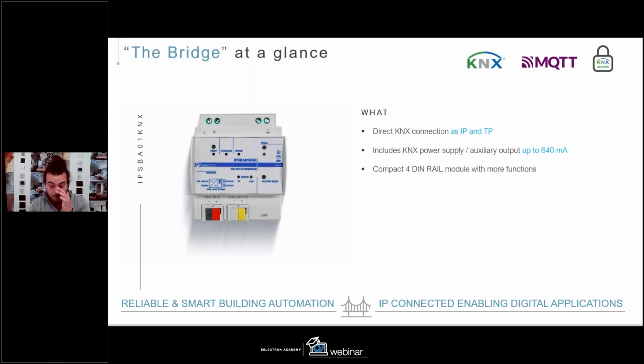Regarding this device, I want to remind you that it is an IP interface, so a gateway between a twisted pair cable of KNX and the IP world. It is also a power supply for KNX and has the auxiliary power supply, and the total output could be maximum 640 milliamps. The dimension is very compact, since this model will occupy only 4 modules on your electrical board. This can help you to reduce the cost of the installation and of the project, because the cost of this device will be less than one power supply plus one IP interface.